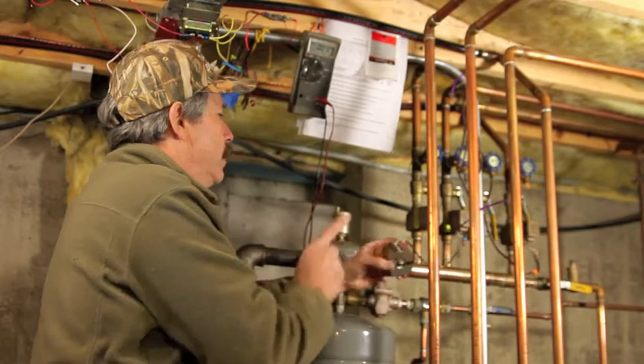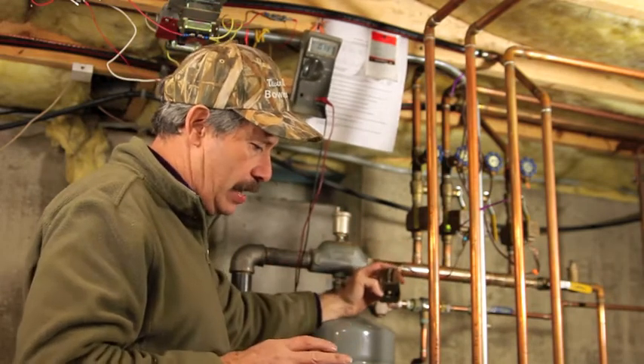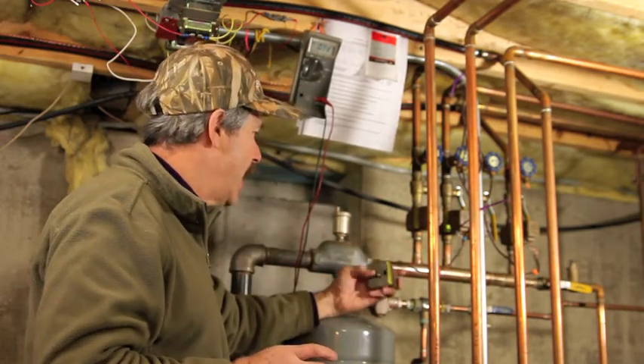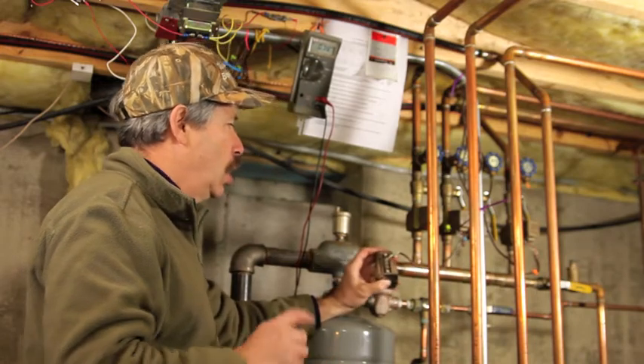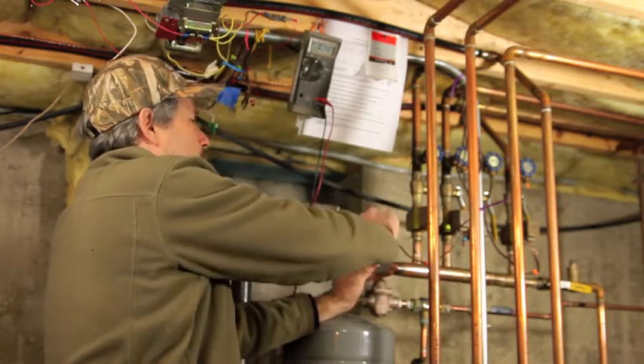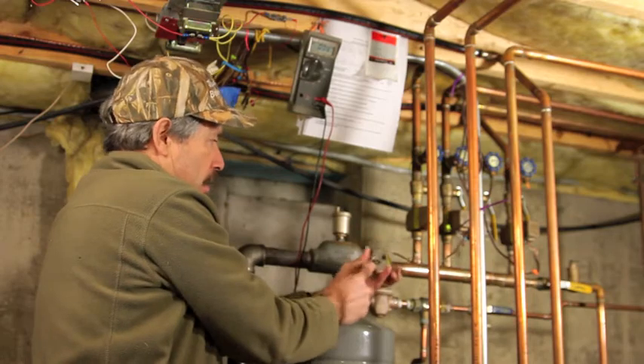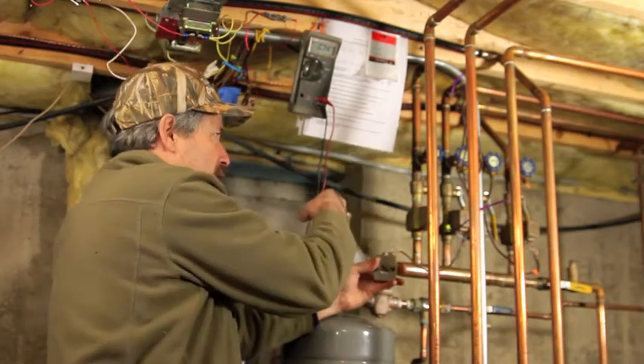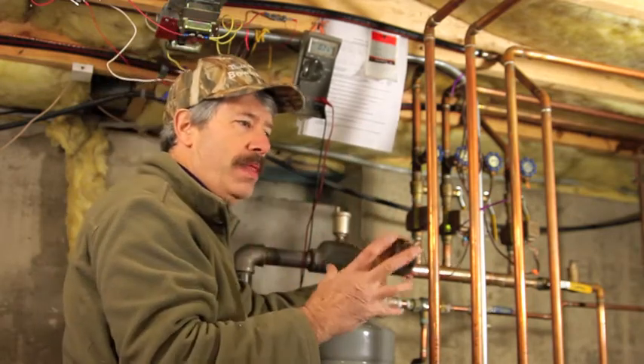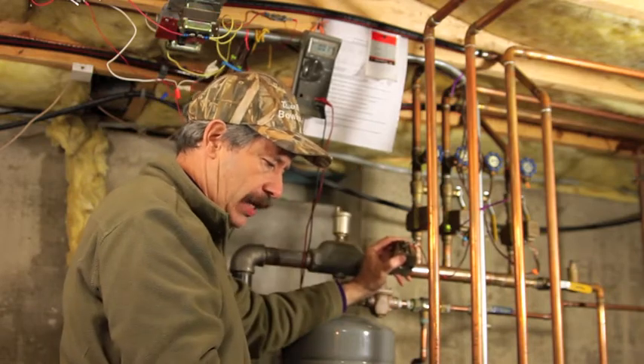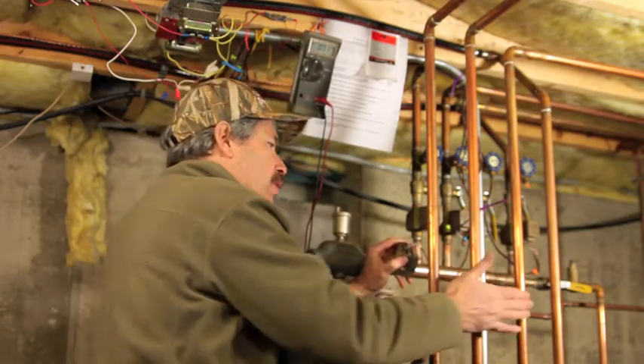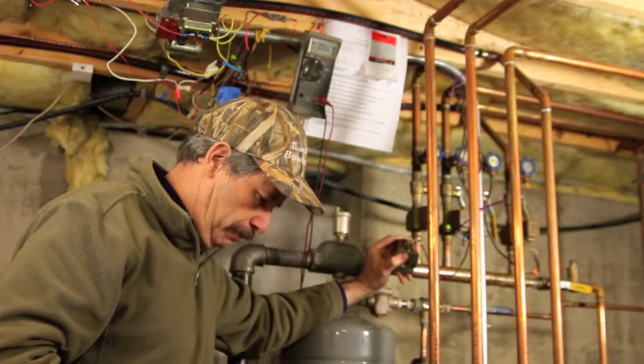Now, if something goes wrong and we lose the thermostat upstairs, you can pull with this mechanical lever, you can pull it forward and it pushes the zone valve so that it's open. The zone valve open, anytime the circulator's on, water will flow through that zone at that point.